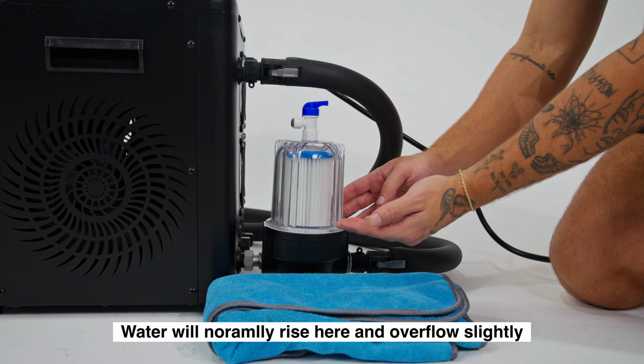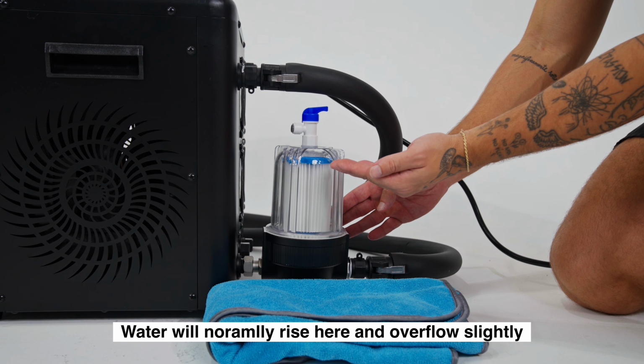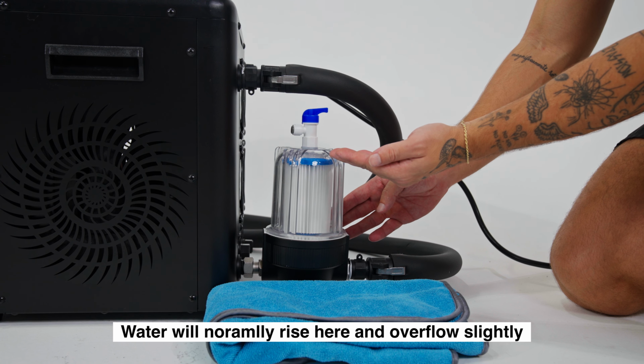Once the canister fills about 3/4 of the way and water begins to come out of the vent, go ahead and tighten the vent to close it. Now it's time to power up the system. On the plug, press the safety reset button to activate power. You'll usually hear a small click when it engages. Then press the power switch on the back of the chiller. You'll see the screen light up. Your chiller is now running.